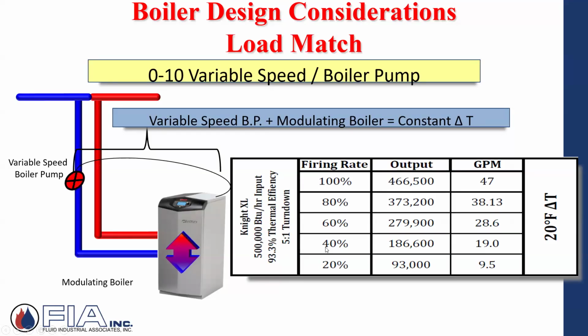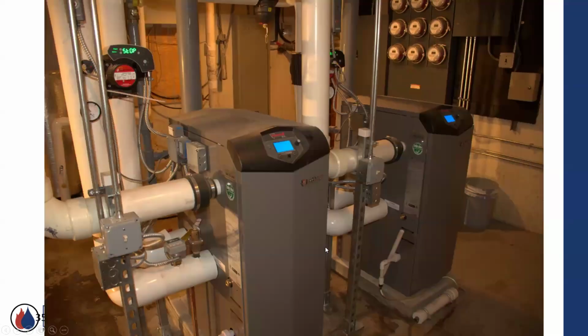variable speed, I can't even speak here at the end of the day, variable speed pump, I can now maintain a fixed delta T across my heat exchanger by changing the flow rate through the boiler to match the firing rate of the boiler. So these high efficiency boilers have intelligence on board that they'll send out a 0 to 10 or a 4 to 20, and they'll be looking at their sensor right here at the inlet of the heat exchanger and the sensor right here on the outlet. And if you dial in and say, hey, maintain a 20-degree delta T, as it modulates down and you're over pumping, that delta T gets tighter. So slow the pump down so you increase that delta T back to your desired 20 degrees. So that's another very popular and very important or favorable.